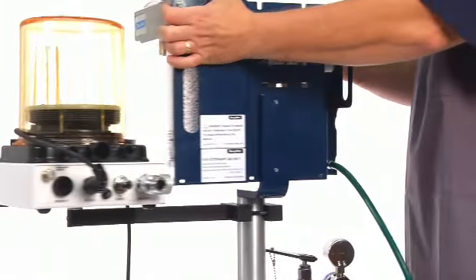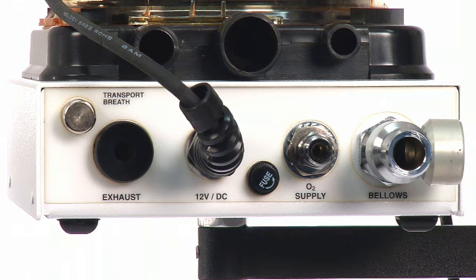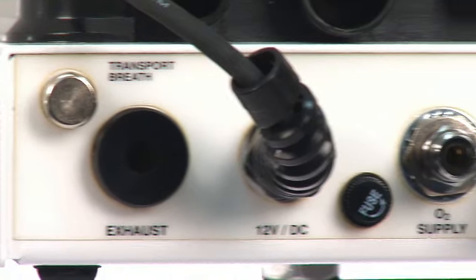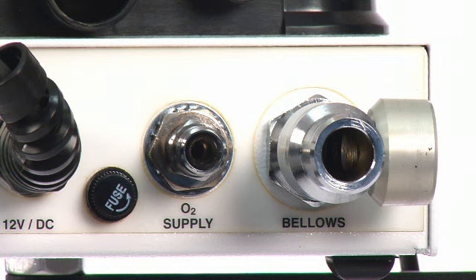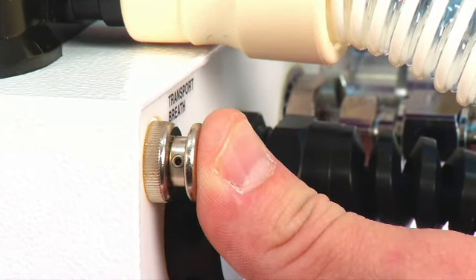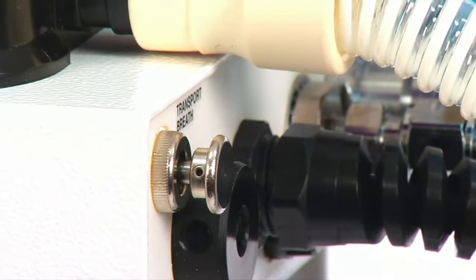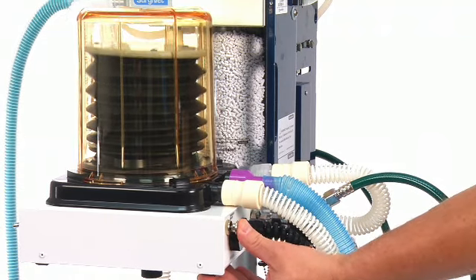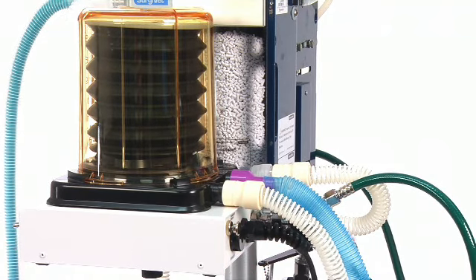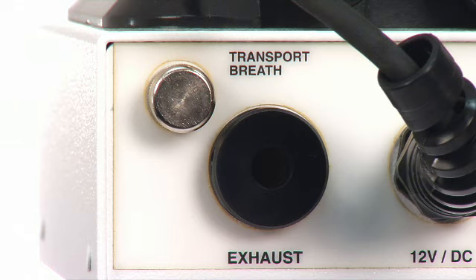Position the ventilator so you are viewing the back side of the control head. The adapters will be attached in order from left to right. On the far left side, you will see the transport breath button. This is a pneumatic control that can be used during transport or power loss. The exhaust port is where the drive gas escapes, and scavenging is not necessary on this port.